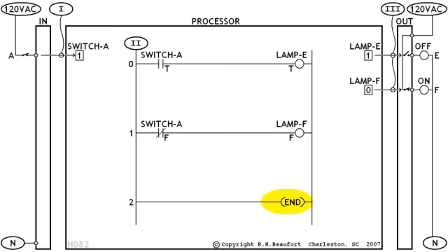to the end rung. And now for step 3 of the scan cycle. There's a 1 in the bit, so the processor goes to the module and gives it a signal to turn the output on. There's a 0 in this bit, so the processor goes to the module and gives it a signal to turn the output off. And we're through with this scan cycle. And unless something changes, that same sequence gets repeated several hundred times each second.